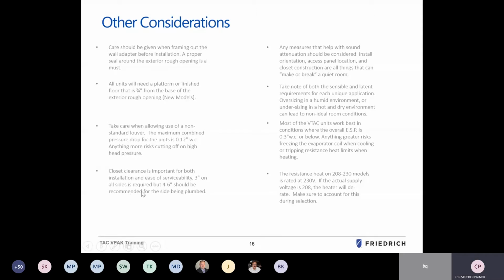More importantly, this is a common one that often is questioned. Installation and serviceability, 3 inches on all sides is required. The recommended 4 to 6 inches should be provided on the side for the plumbing connections or your condensate drain connections, to allow for the PVC piping, to make sure that there's enough room for the piping once you close the closet door or that you have service access to it. That's a critical measurement there in that regard, as far as being able to make appropriate consideration for the drain connections.